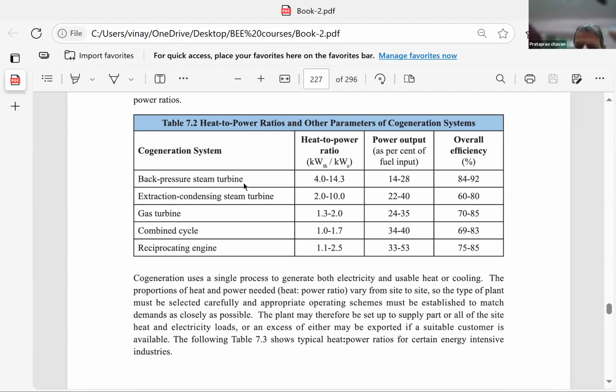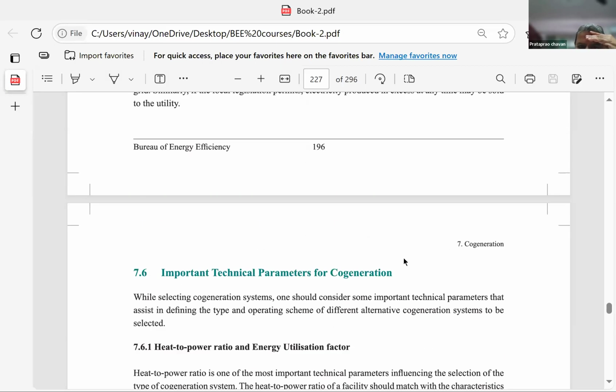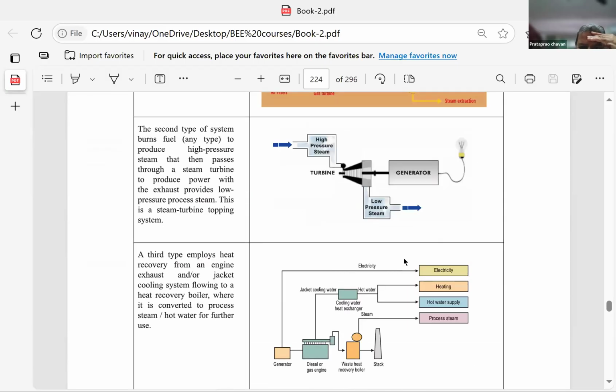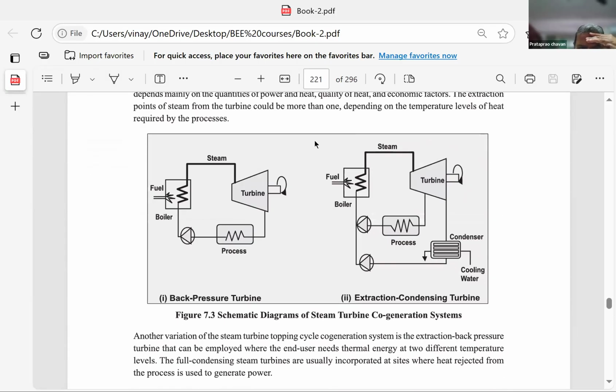Back pressure steam turbine — the first diagram, where there is no condenser. Yes, it's here: the back pressure turbine. What are the components? Boiler, turbine, no condenser. Whatever the turbine rotates goes to electricity, but a chunk of the steam at a certain pressure and temperature is utilized mainly for the process. Here the heat is completely utilized, giving very high efficiencies, but the power component is very small while the heat component is the major use.